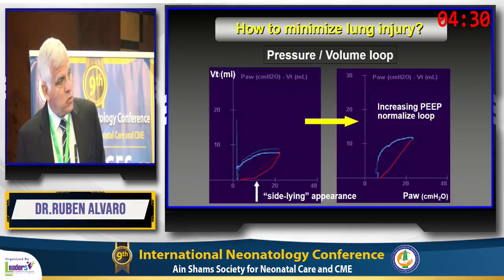Always look at your volume pressure loop to see where your compliance starts changing, and the angle of that compliance - it should be around 45 degrees. This is too flat here, meaning you have low PEEP and your compliance is too low. So you should increase the PEEP and aim for a 45 degree compliance.